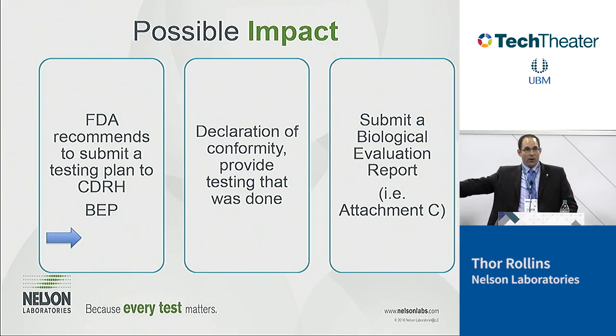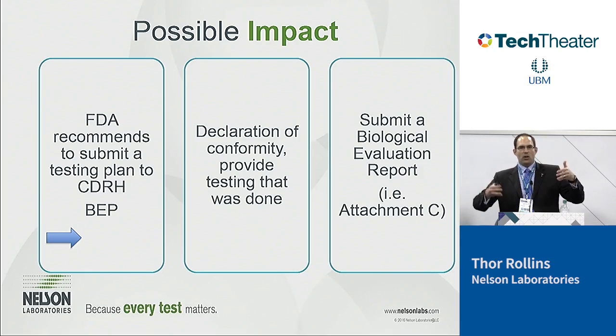Okay, so here's one of the first things that I've seen that is different. We call it a biological evaluation plan. But in this document, the FDA says, we want you to develop a risk-based plan before you start testing. Submit that plan to them, either formally or informally, to get feedback. Now, this is a really good way to try to get out of some testing, or if you have a very complicated device, to get feedback from the FDA. So we do something called a biological evaluation plan, or BEP, but it's really just a risk-based plan. What you do is you look at your device, the materials, and the processing, you evaluate the risk to the patient, and then you come up with a plan on how to mitigate that risk. And it may be chemistry, it may be a risk assessment in the document itself about why you don't need testing, all these different endpoints, and then you can give that plan to the FDA.